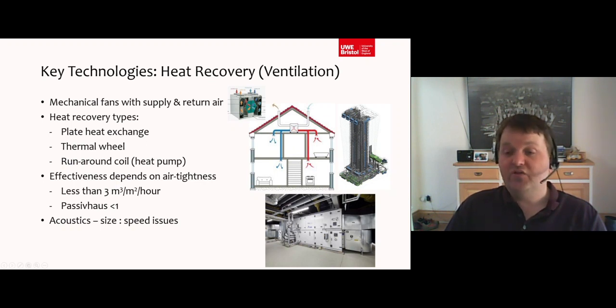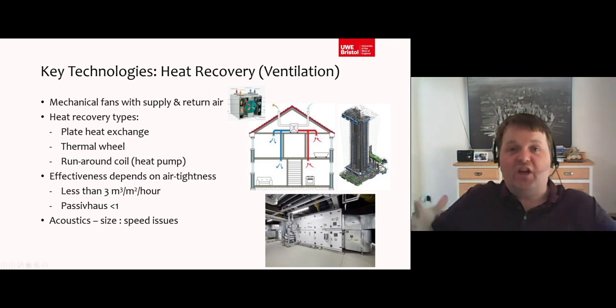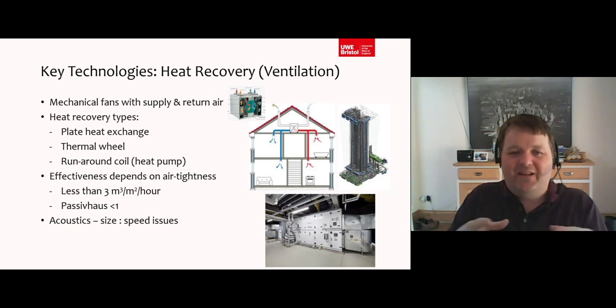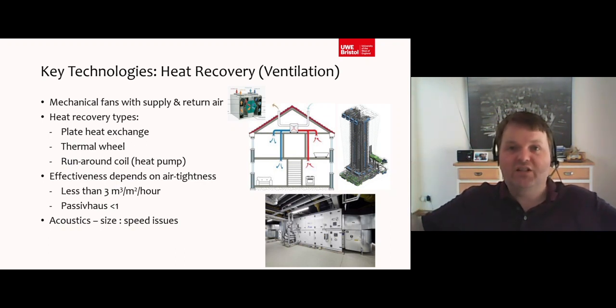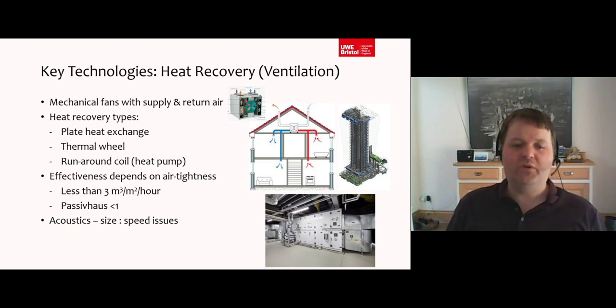Also, just in big industrial facilities, if the architect is tight about how much space they give the air ducts, then those air ducts need to be smaller. And to perform, we may have to pump more air down through them. And the faster air you have, the noisier you're going to get. If you want to quieten that air, the solution is often space. So like in a music venue, you're putting in the air conditioning as a big gentle giant because it's moving a lot of air, but quite slowly through the system in order to provide comfort to people sitting in an arena, because you don't want the noise to be interrupting the lecture theatre. So acoustics is a really important aspect of making this system work.